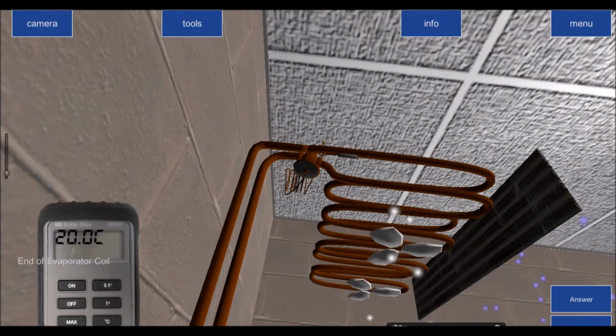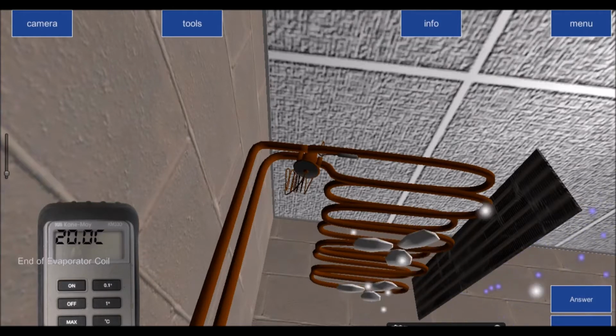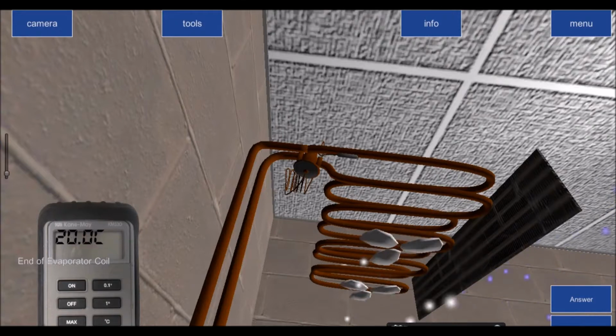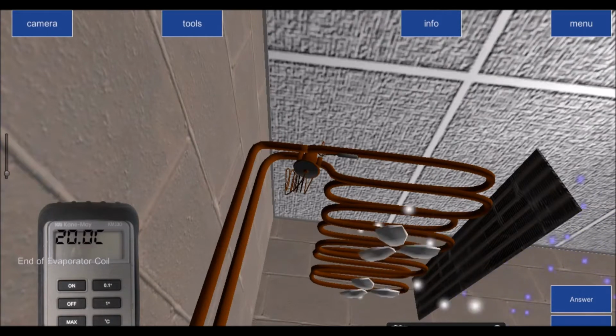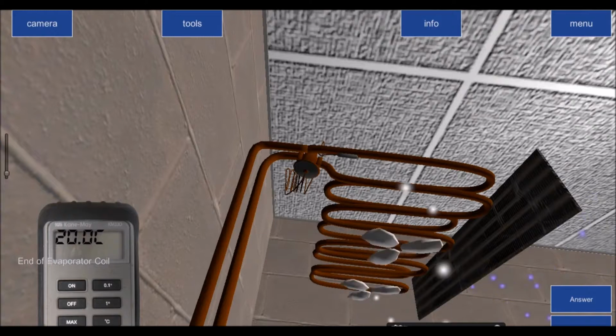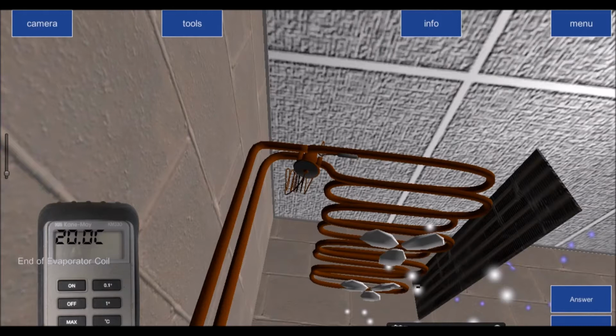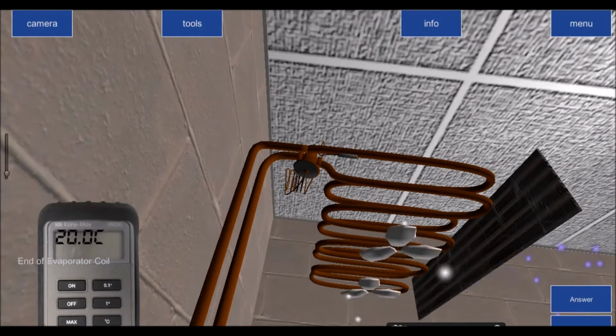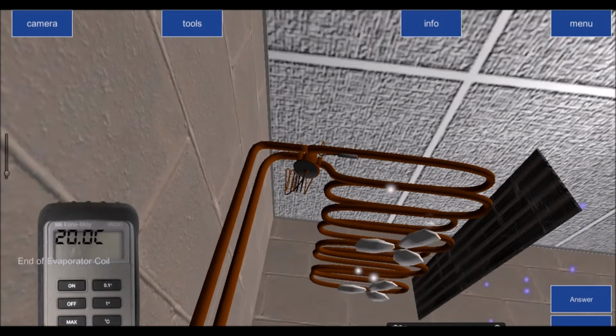So only the proportion of liquid that's needed to boil off to remove the heat boils off. And then you will find that back at the compressor, before the suction pipe enters into the compressor, a suction accumulator is fitted, and that suction accumulator will separate the liquid from the vapor. And again, when you come back to site, there is a slide which shows you a suction accumulator, and I'll explain that to you as well. But when you come back to site here, I will actually show you a physical suction accumulator that I've taken the sides out of, so you can see into it, for a split air conditioning unit and for a commercial refrigeration unit. You'll see how they work then as well.